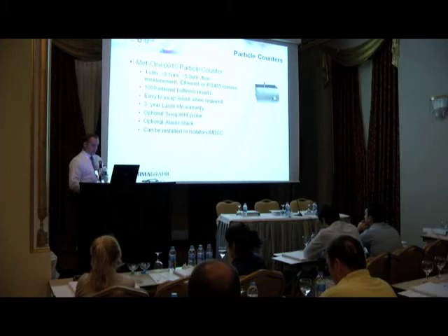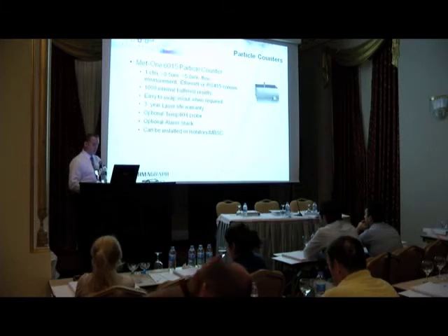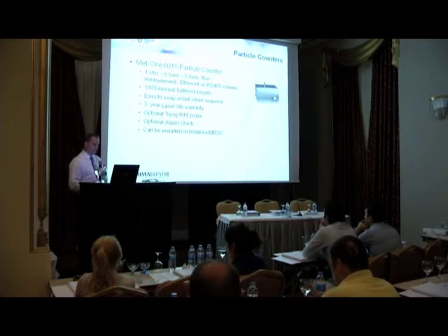The device has 1,000 internal buffered results, which is important because it gives you some robustness against system failure, because data can be retrieved at a later date. Counters are easy to swap in and swap out when required. They have a 3-year warranty on the laser life, and they should last at least 10 years. And you can connect an optional temperature humidity probe.